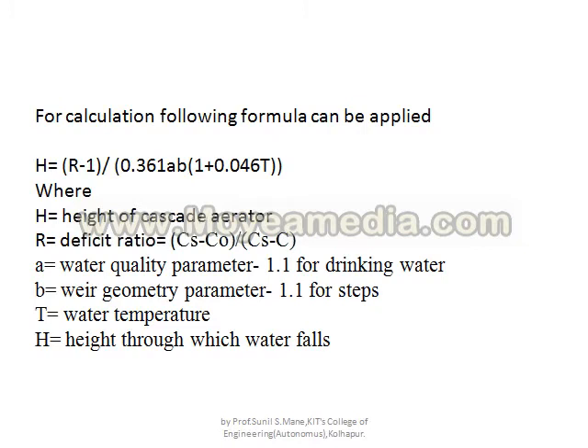R is the deficit ratio, calculated as: (saturated concentration − initial concentration) / (saturated concentration − required concentration). A is the water quality parameter — for drinking water, A = 1.1. For wastewater and other types of water, this factor will be different.